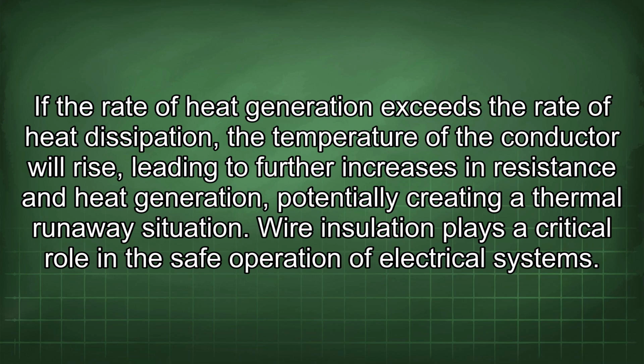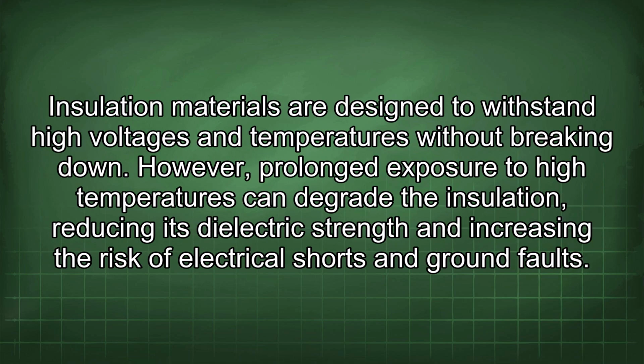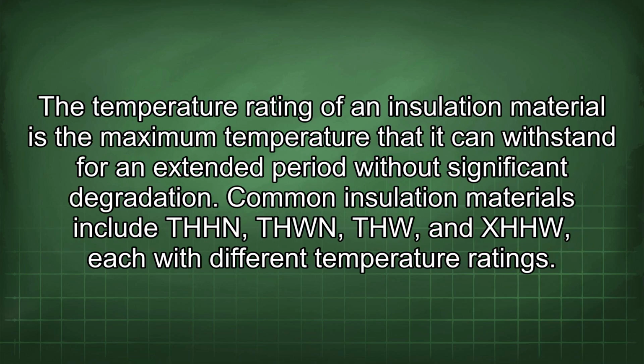Wire insulation plays a critical role in the safe operation of electrical systems. Insulation materials are designed to withstand high voltages and temperatures without breaking down. However, prolonged exposure to high temperatures can degrade the insulation, reducing its dielectric strength and increasing the risk of electrical shorts and ground faults. The temperature rating of an insulation material is the maximum temperature that it can withstand for an extended period without significant degradation.